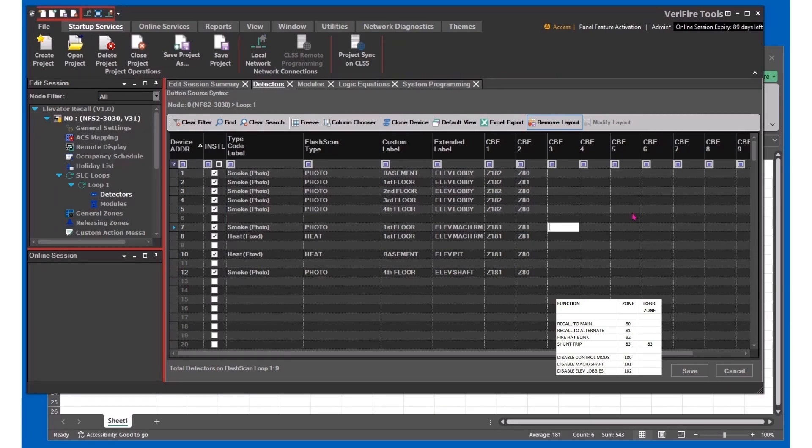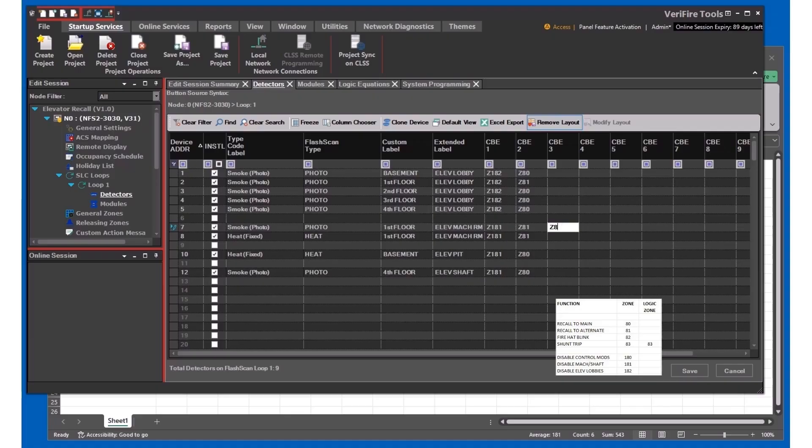With the basic recall groups programmed, now we can do the special function groups. So the machine room detector, we want it to blink the elevator hat, so we'll do 82. Same thing for the heat detector.